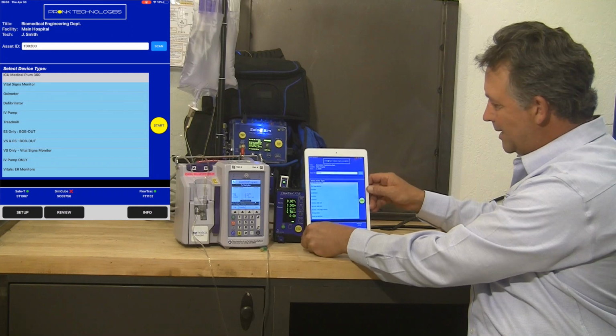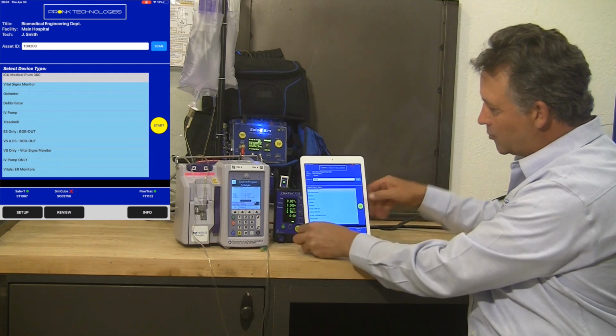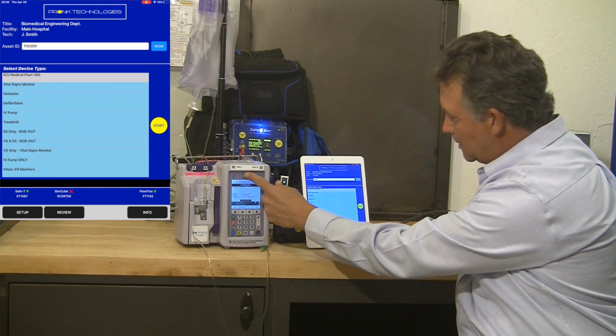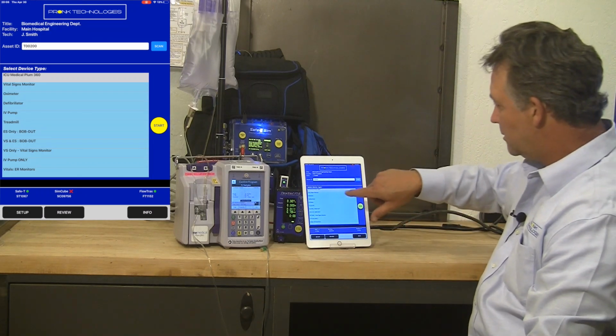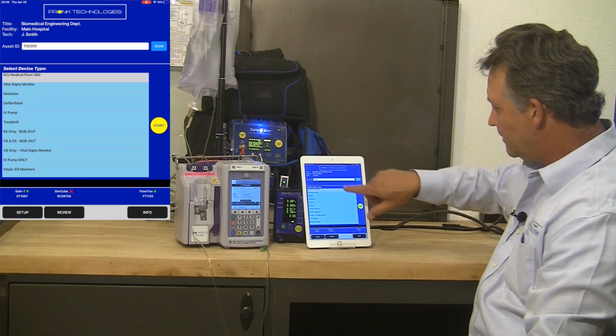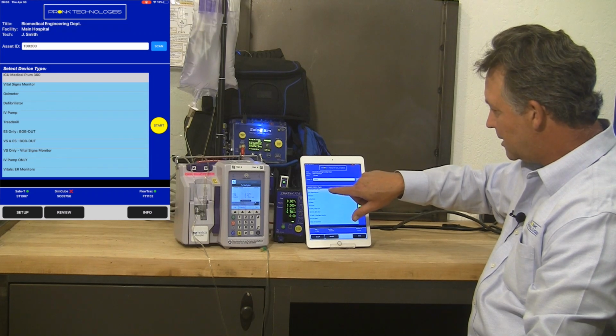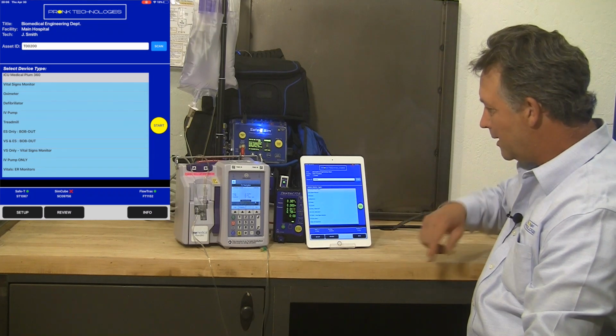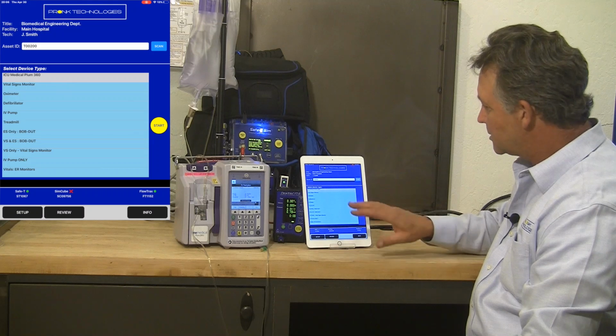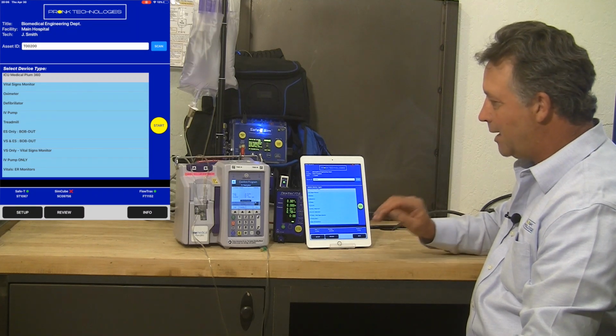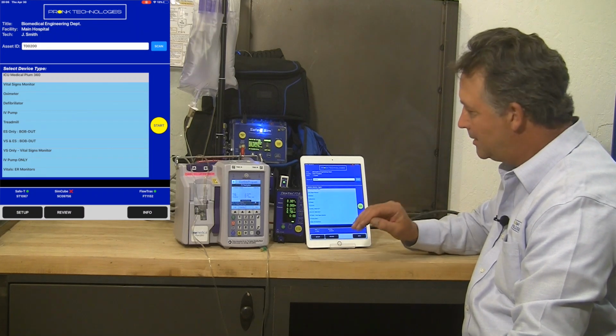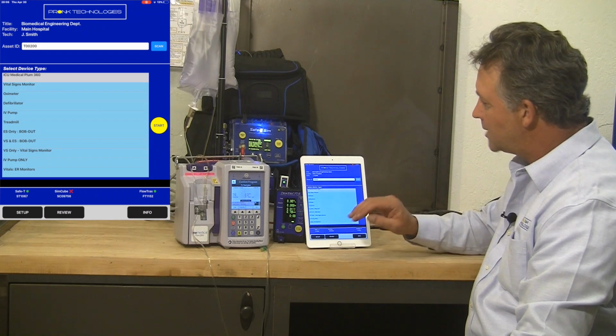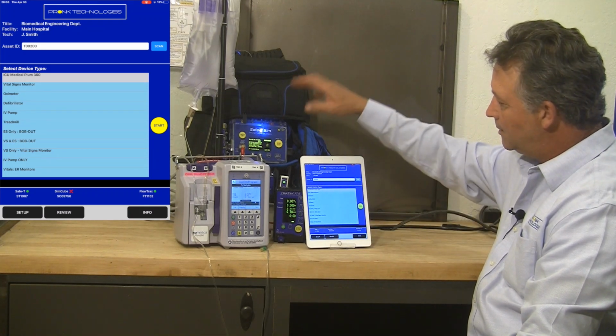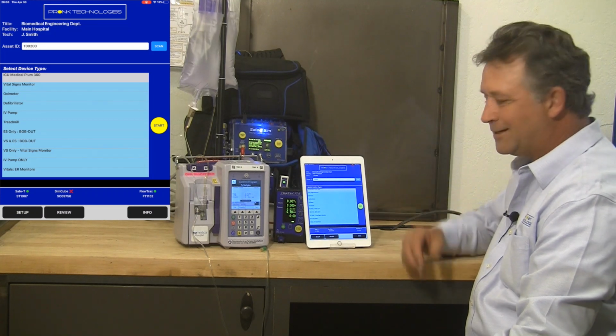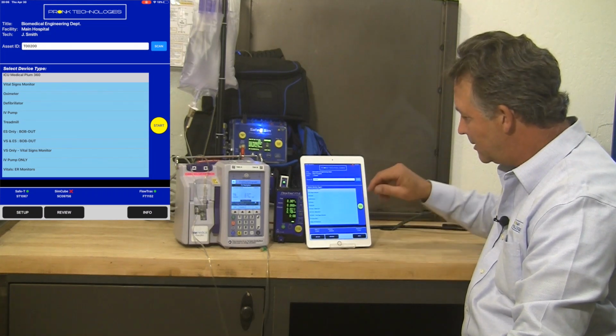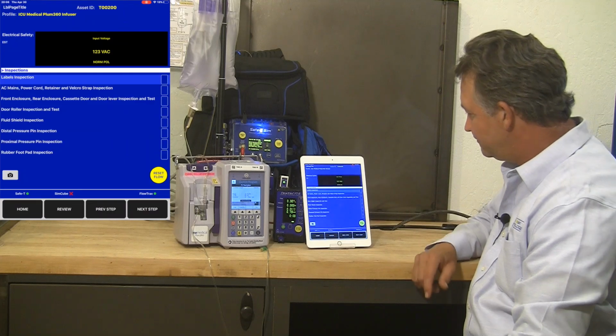Get the asset ID pulled into my test record at the start so that I can have that all the way throughout, all the way to my electronic record. From here, I can select the device type. In this case, it's already selected ICU Medical Plum 360. I'm going to start that test, and we're going to use the actual manufacturer detailed checklist to run through this test wirelessly, controlling the test devices and capturing back detailed records into the iOS device. I'm going to go ahead and hit start.